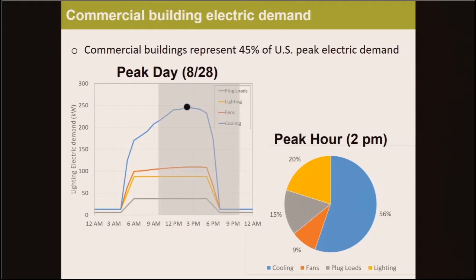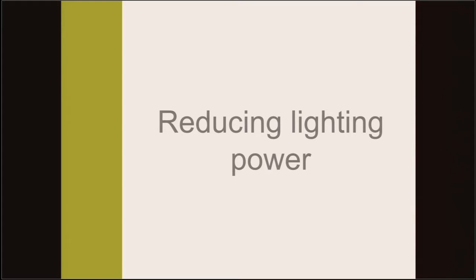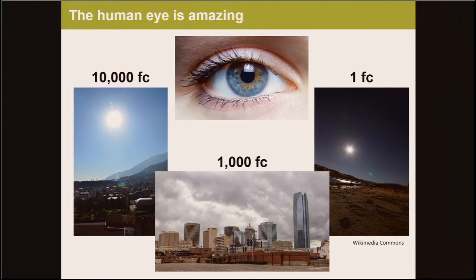A nice side effect of reducing lighting power is that cooling load is reduced as well, usually between 10% and 20% increase in the total reduction. Now, the main question is whether there's anything we can do to reduce lighting power. We could turn out all the lights, but unfortunately we need those lights to do our jobs. So lighting power and the available light, or illuminance, are essentially linearly related, which means we first have to understand more about how our eyes work and how much light we actually need.